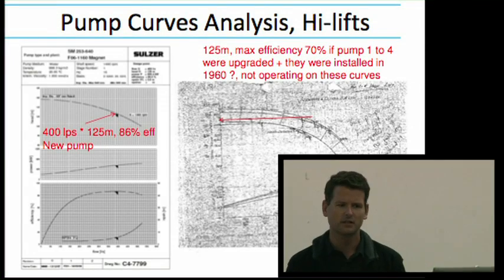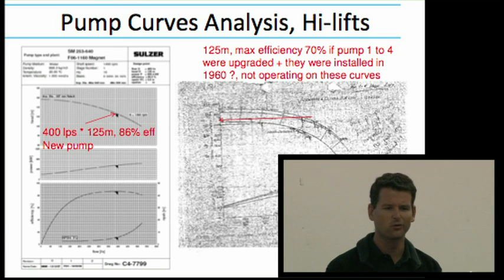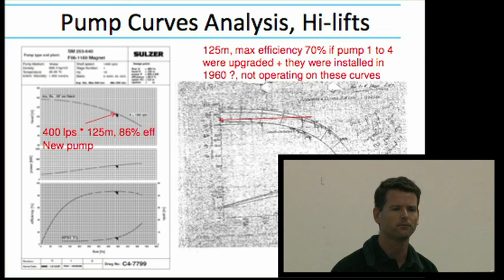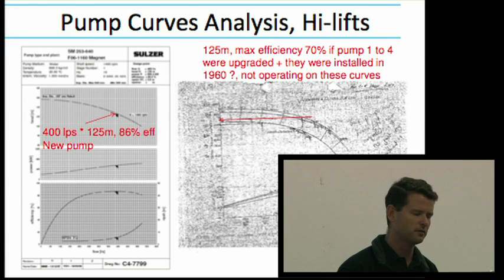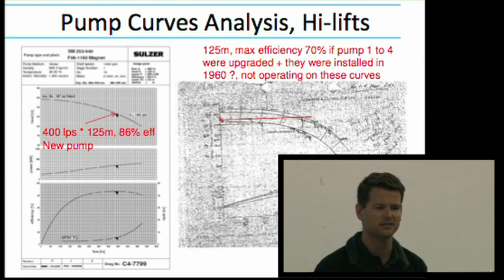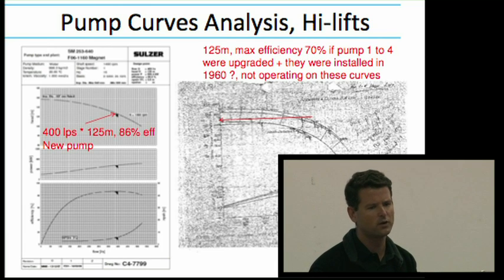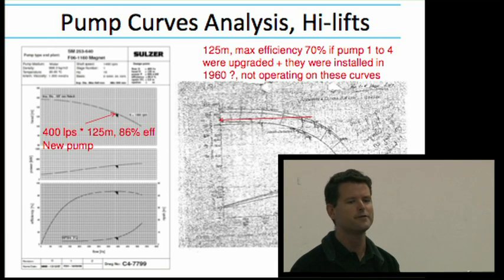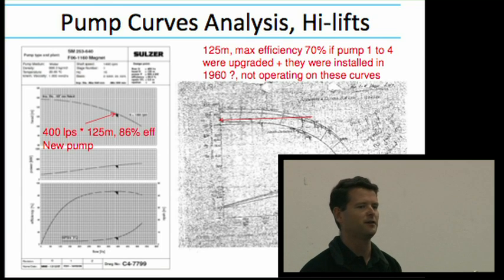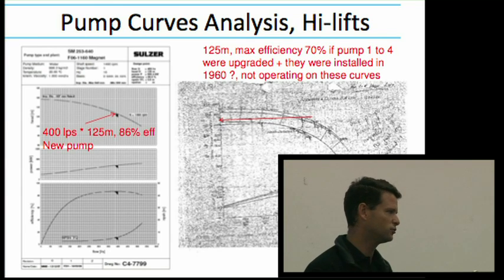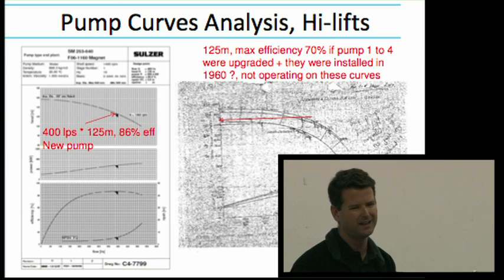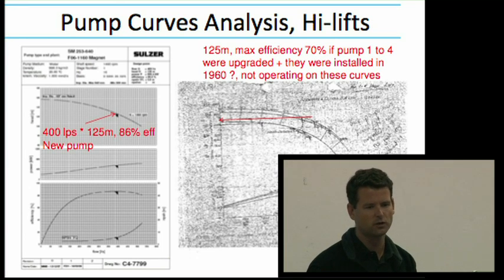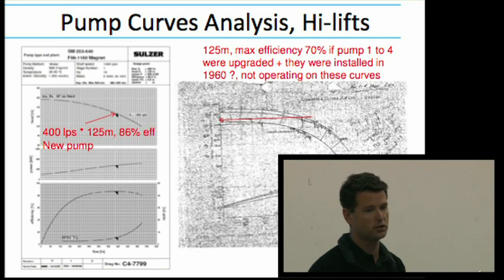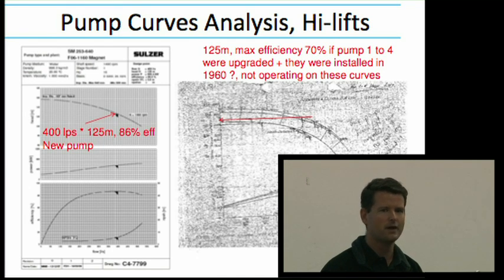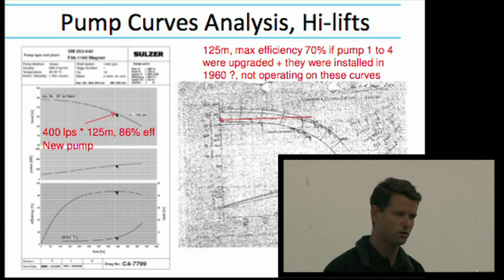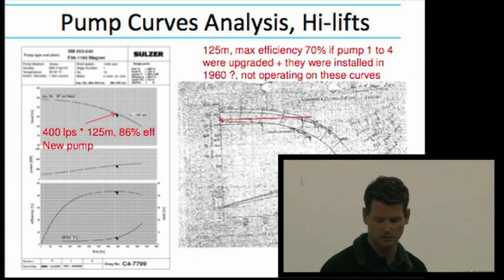So on the high lift pumps, the existing pumps, pumps 1 to 4, were sitting at about, we thought, 70% efficiency. The bigger, more efficient pump was sitting at a theoretical 86% efficiency. So one of the questions you've got to juggle as well is, in theory, you can upgrade the smaller pumps and put in bigger motors and do that whole analysis. Do you believe that they're going to be operating on their pump curves and that sort of stuff? And fortunately, it worked out that it was more cost effective to put in a new, more efficient pump, because I was very wary of believing the existing pumps that were so old would actually give me the performance that their curves were telling me that they would.